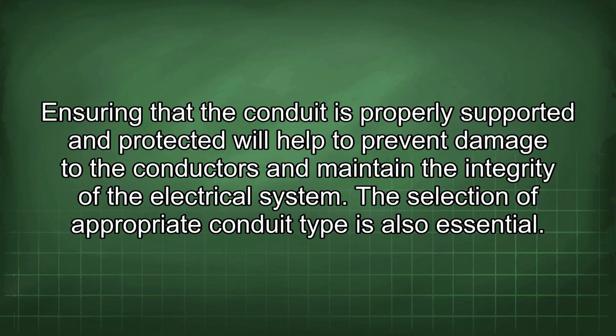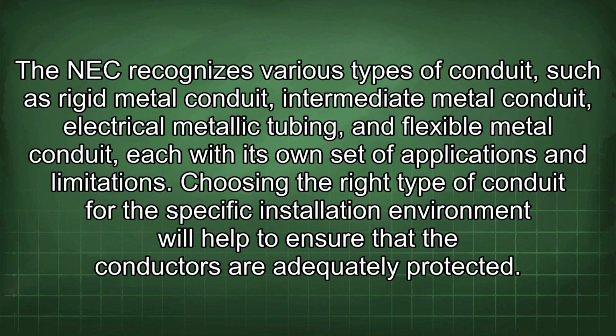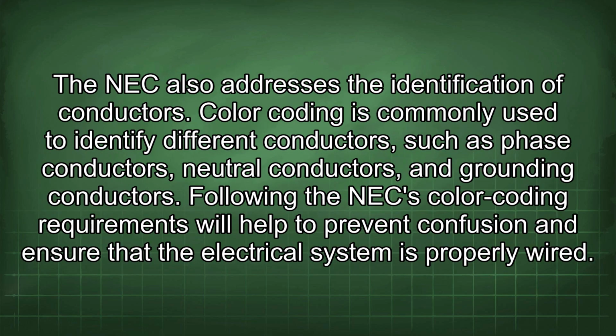The selection of appropriate conduit type is also essential. The NEC recognizes various types of conduit, such as rigid metal conduit, intermediate metal conduit, electrical metallic tubing, and flexible metal conduit, each with its own set of applications and limitations. Choosing the right type of conduit for the specific installation environment will help to ensure that the conductors are adequately protected. The NEC also addresses the identification of conductors.